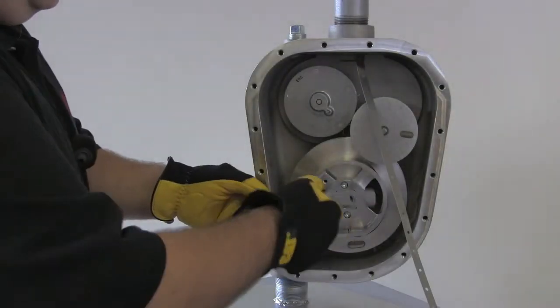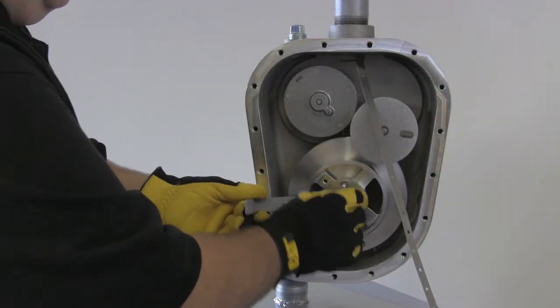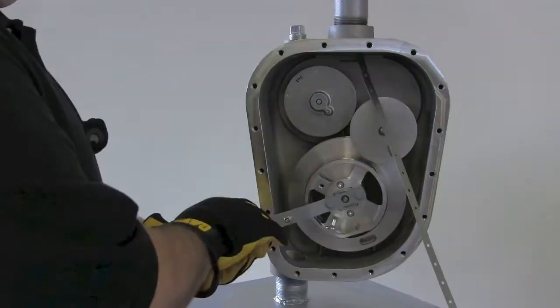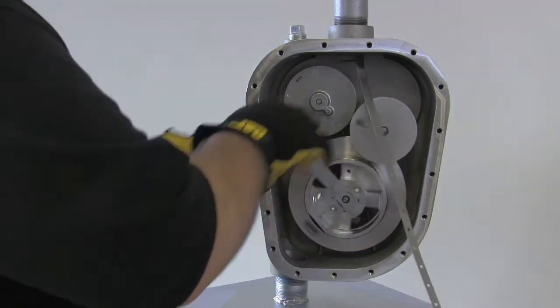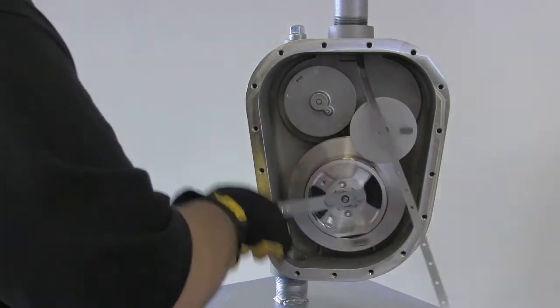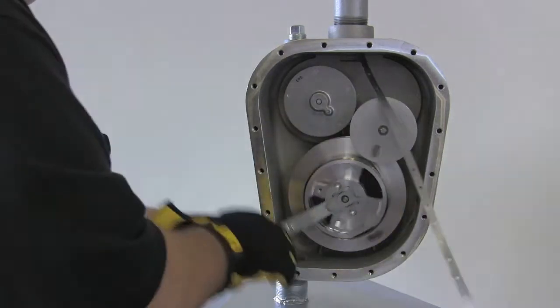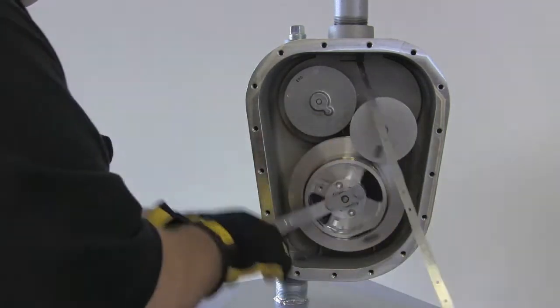First, attach the crank to the tape storage sheave. Loosen the thumb screw, then wind the storage sheave clockwise. The number of turns required is dependent on the height of your tank. Refer to the manual for the exact number, but it's about 45 turns for a 60 foot tank.